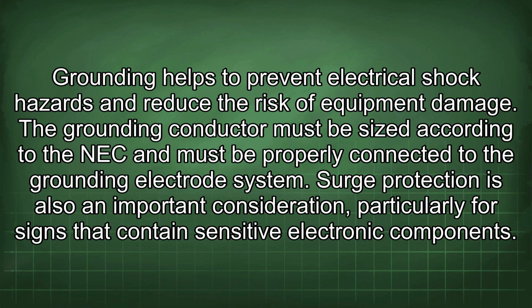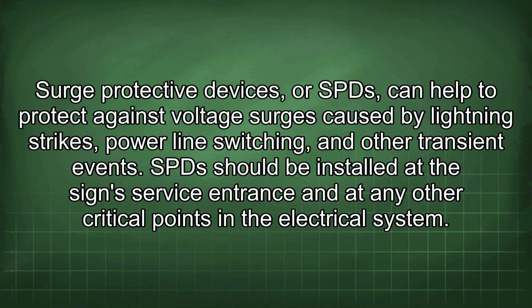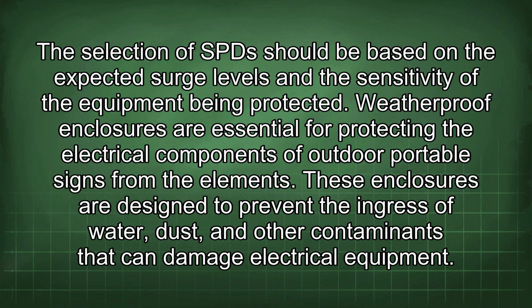Surge protection is also an important consideration, particularly for signs that contain sensitive electronic components. Surge protective devices, or SPDs, can help to protect against voltage surges caused by lightning strikes, power line switching, and other transient events. SPDs should be installed at the sign service entrance and at any other critical points in the electrical system. The selection of SPDs should be based on the expected surge levels and the sensitivity of the equipment being protected.